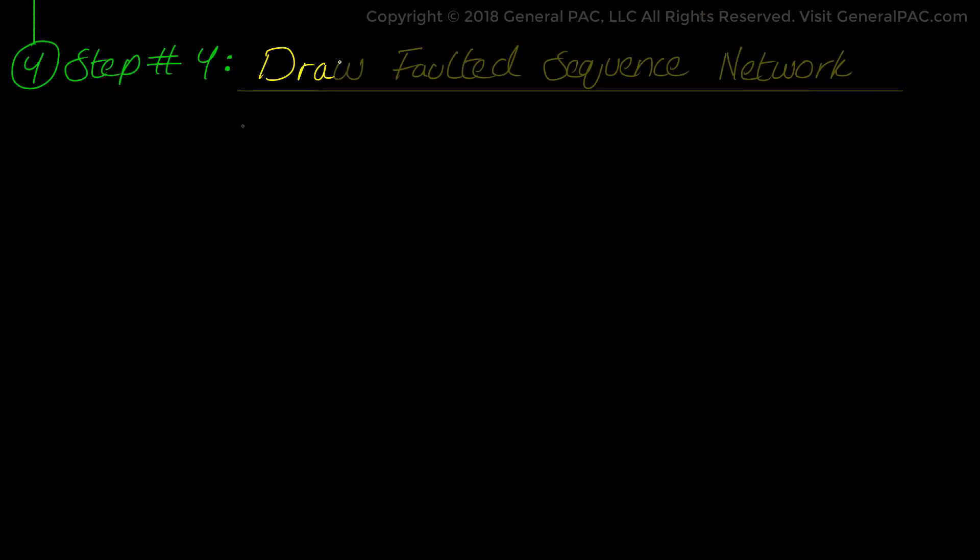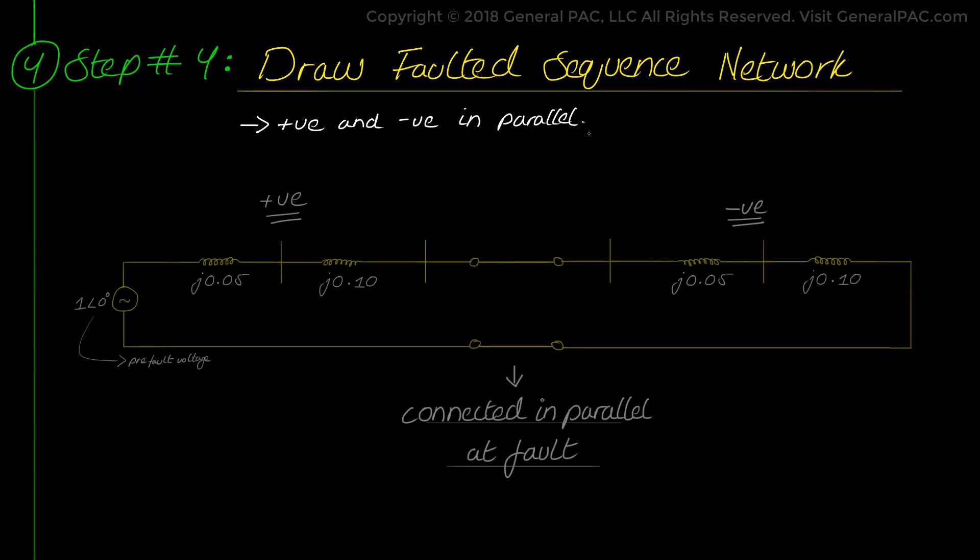And then in step number 4, we will draw the faulted sequence network based on the type of fault we have. Now, given that the fault is a line-to-line fault as we mentioned before, we will connect the positive and negative sequence networks in parallel. This we will discuss in great detail in our video on a line-to-line fault in topic 2 which is the derivation of sequence network diagrams of our series. But for now, we will just redraw a parallel connected faulted network.